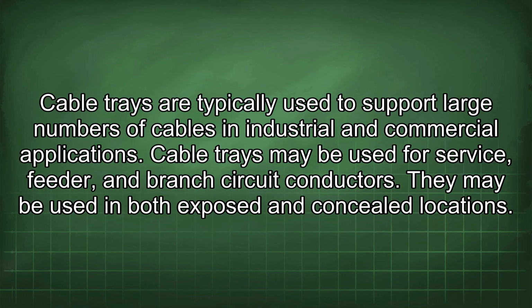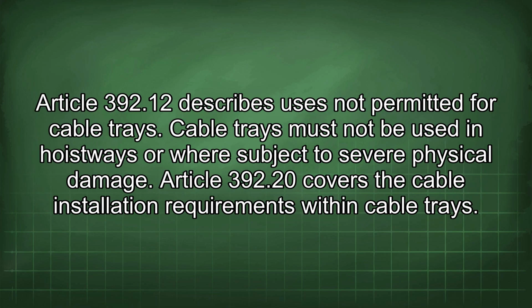Cable trays are typically used to support large numbers of cables in industrial and commercial applications. Cable trays may be used for service, feeder, and branch circuit conductors. They may be used in both exposed and concealed locations. Article 392.12 describes uses not permitted for cable trays. Cable trays must not be used in hoistways or where subject to severe physical damage.